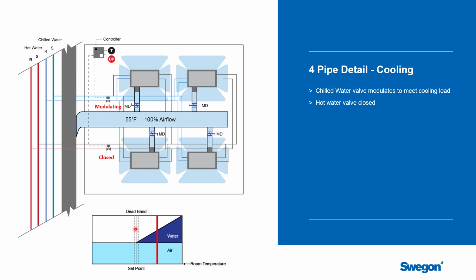Let's have the situation where we see a cooling load in the space. So you can see the room has moved out of the deadband up into here, and so we're going to start to modulate chilled water through the beams to help getting some cooling effect. And so the hot water valve will stay closed, and the controller for that zone will modulate this chilled water valve, allow some water into these beams to meet the cooling load as necessary.